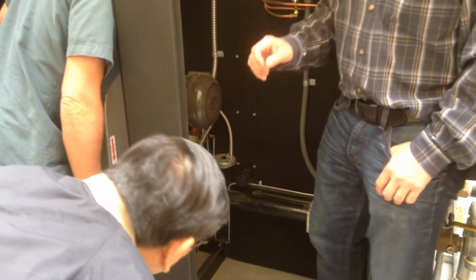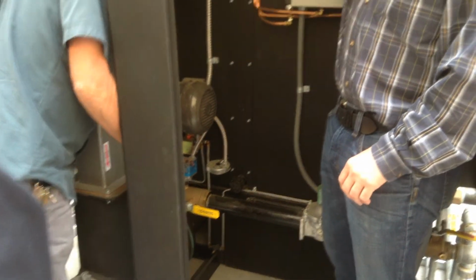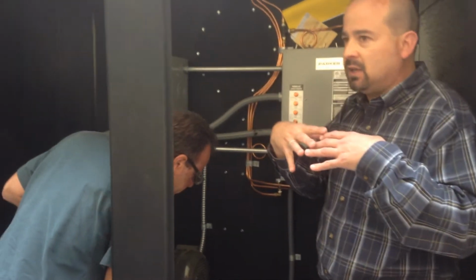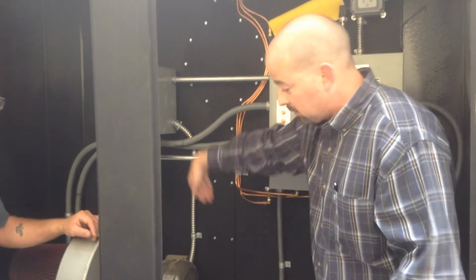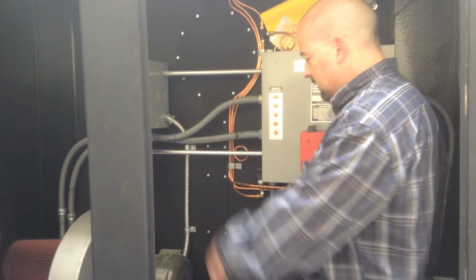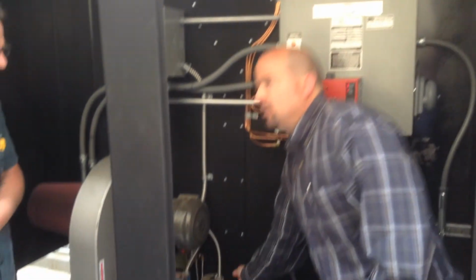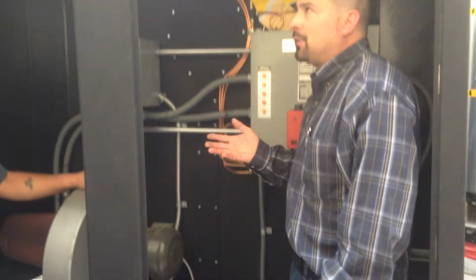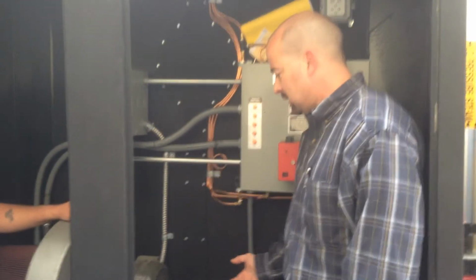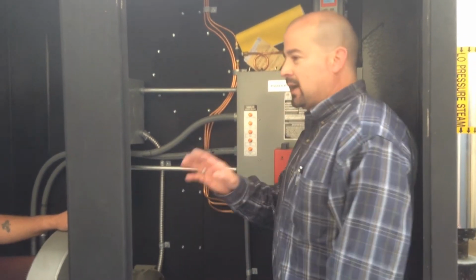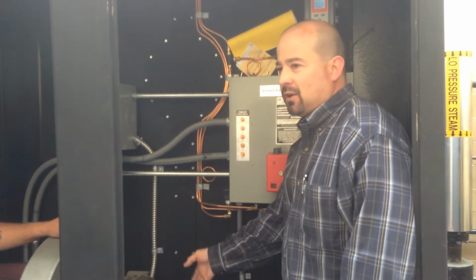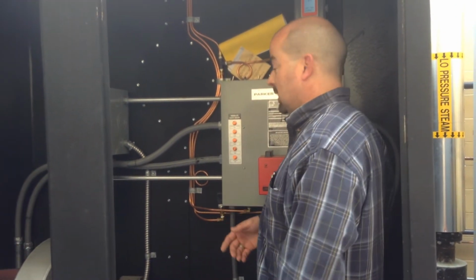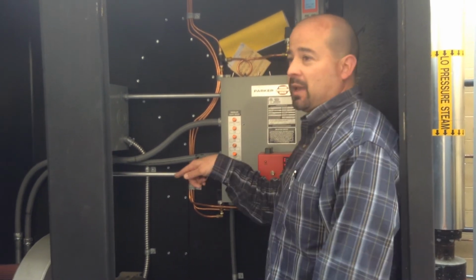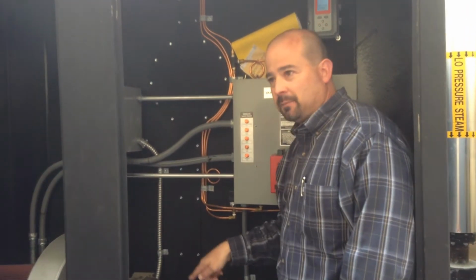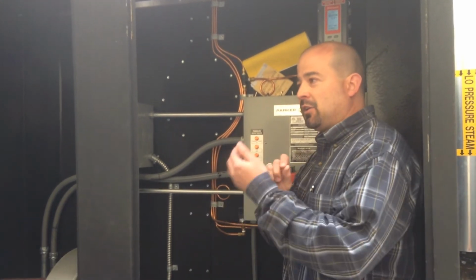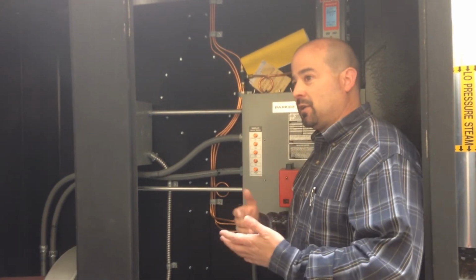This is if something goes wrong, like let's say the flue or the chimney were to get blocked for whatever reason, and the heat is staying in the boiler and it's coming out and it's rolling out into this cabinet. This is a thermal disk sensor. So at 180 to 220 degrees, I forget what the exact setting is, it'll trip. So again, if that happens, you're not going to know it, right? So the only way to know it, either you're pushing buttons or you're opening up the panel and you're looking at the wiring schematic and you're going from top to bottom. My advice is go from top to bottom, document it, and call us and let us know.